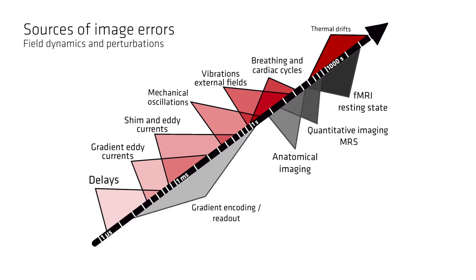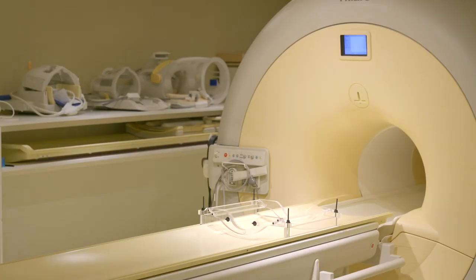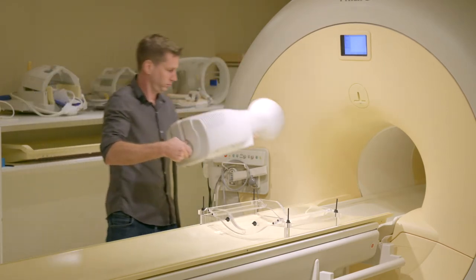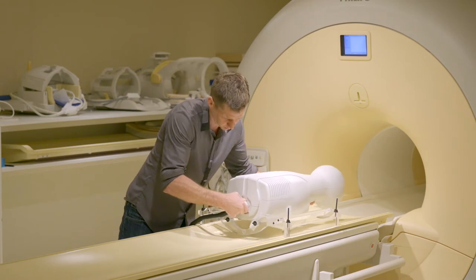To understand and overcome these limitations, I need a tool which acts like an oscilloscope, a tool many engineers use every day to report on the actual performance of the system. Scope tools, including the dynamic field camera, use an array of NMR field probes to report on system performance, very much like an oscilloscope.